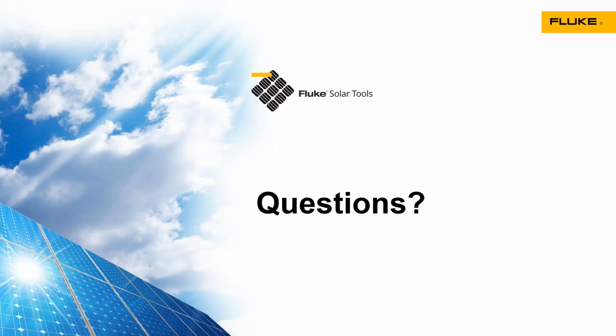The SMFT 1000 will also measure IV curve testing up to 1,000 volts, 20 amps, and currently 19% module efficiency, with soon we'll be able to measure high efficiency modules with our upcoming adapter. It can measure power, so you can measure DC power, measure AC power, and then it will calculate inverter efficiency. It measures open circuit voltage, short circuit current, and polarity.